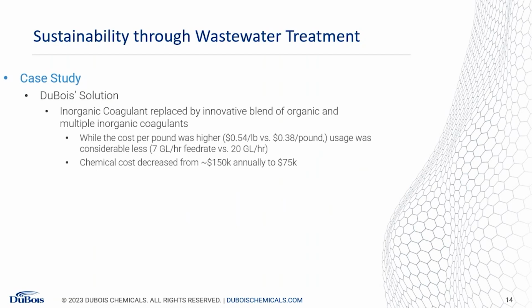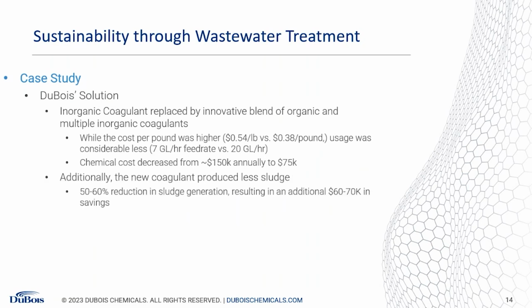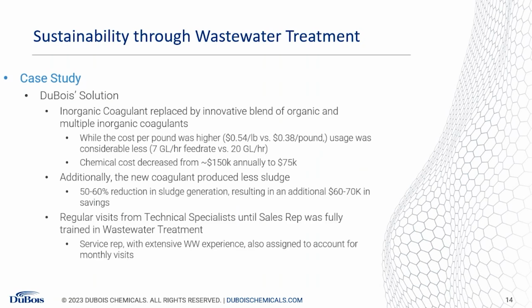This blend was higher cost, 54 cents a pound as opposed to 38 cents a pound, about a 40% increase in cost. But usage was only 7 gallons an hour to treat the water, as opposed to 20 gallons an hour. So yes, the per-pound price was 35 to 40% higher, but we saw a significant reduction in feed rate. As a result, our chemical cost went from $150,000 down to $75,000, higher per-pound price but much lower overall use cost.